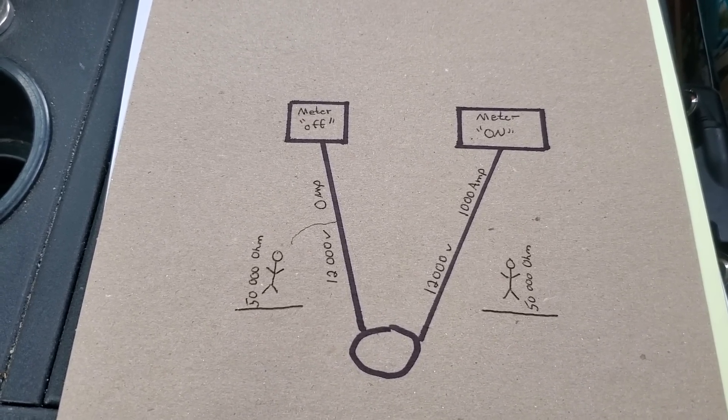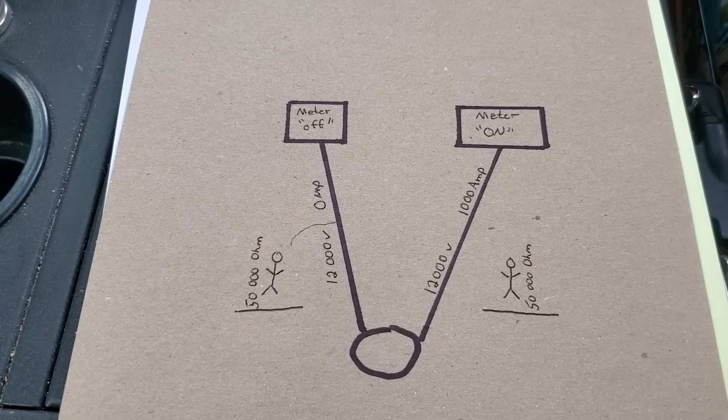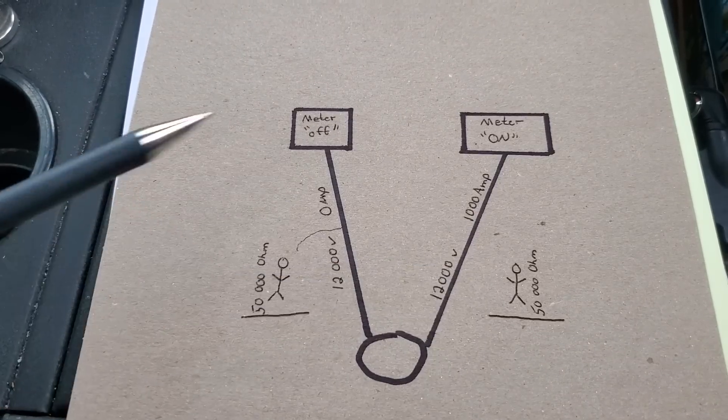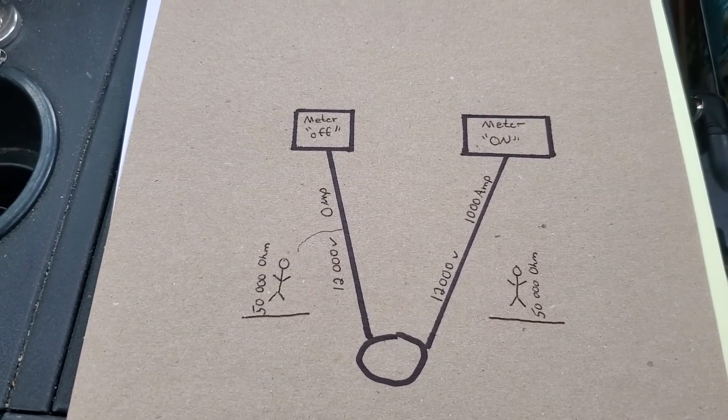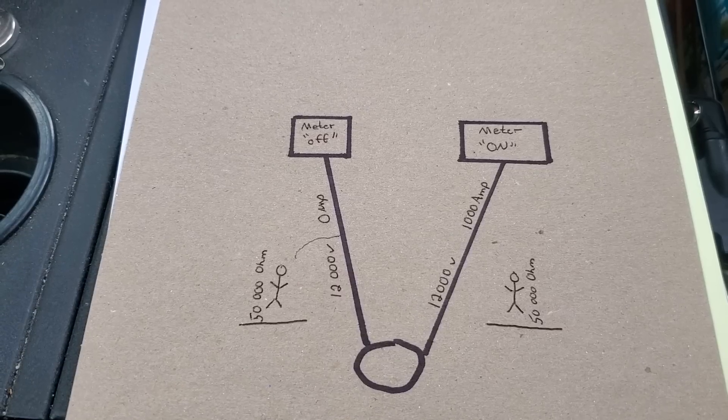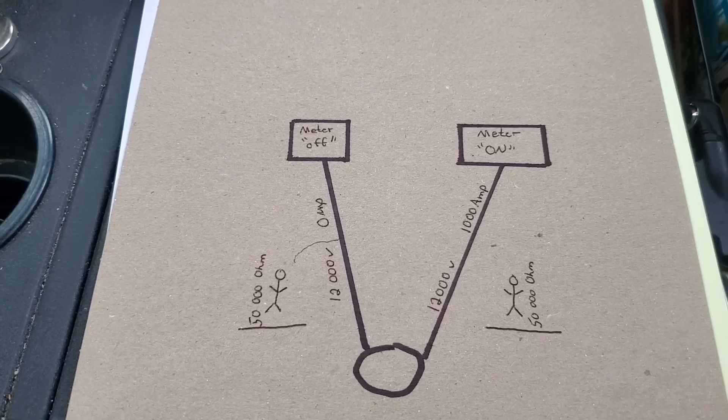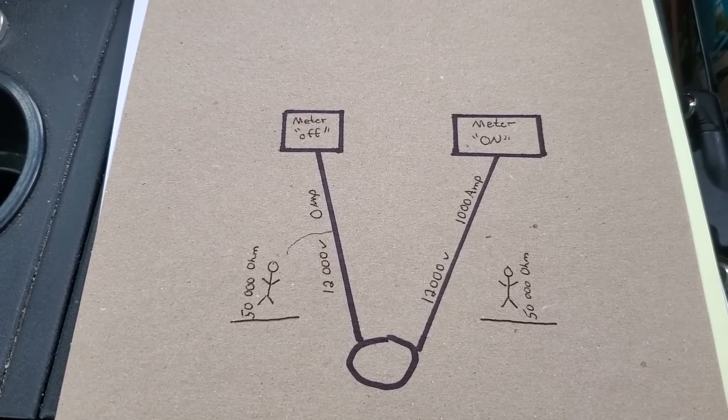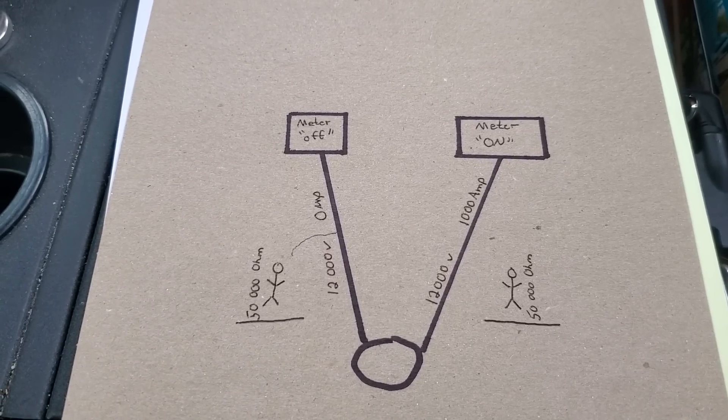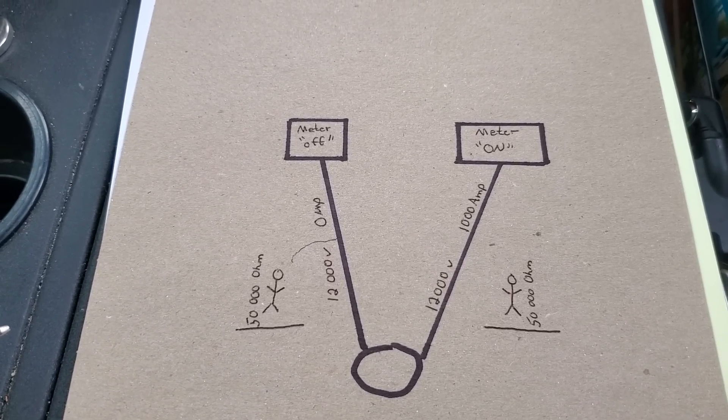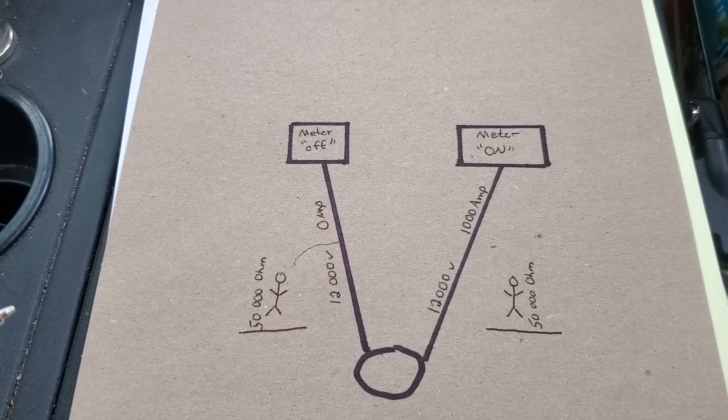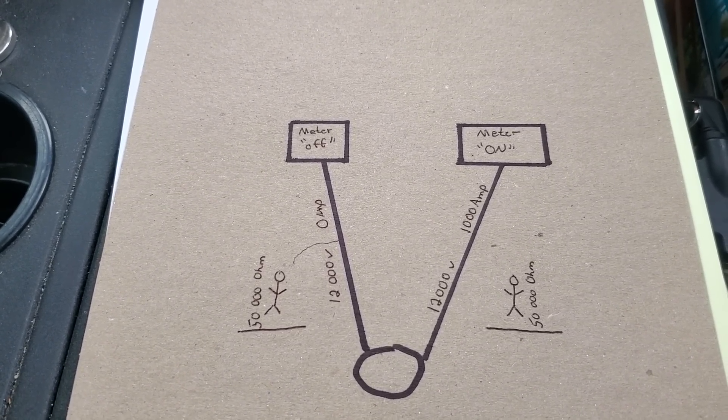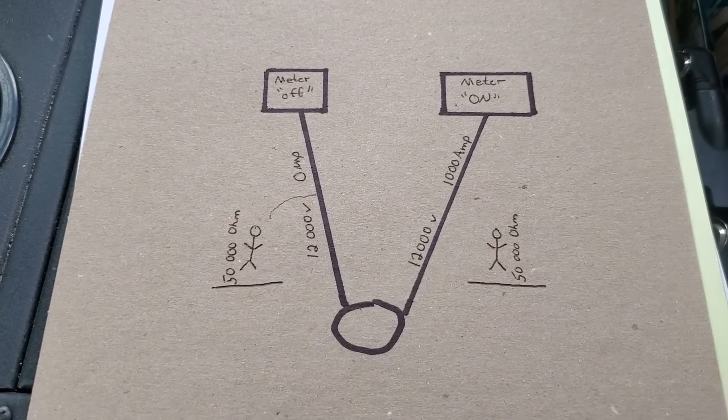You're going to have voltage differences that passes through the body, the resistance is going to be ever changing slightly. You could have your body as low as a thousand ohms resistance if you're standing in a puddle of water on a real hot day and you're sweating, or maybe you've got really good rubber boots on, rubber gloves, at which point you could almost have infinite resistance as long as the voltage can't overcome the insulating properties of your boots and rubber gloves for example.